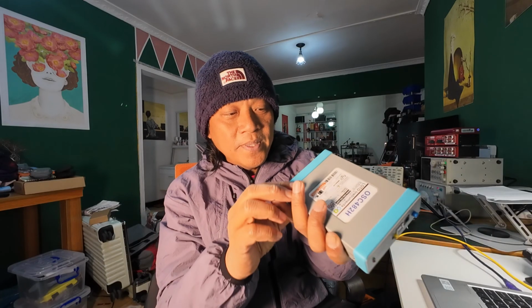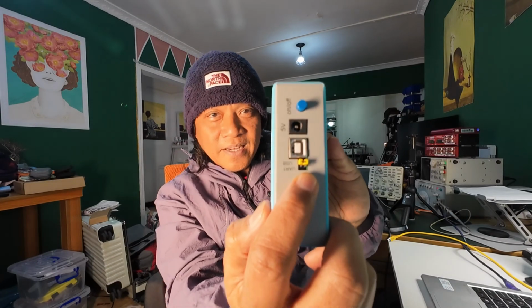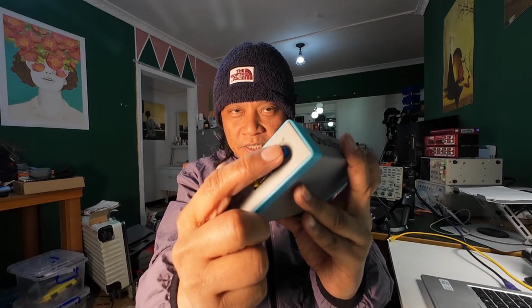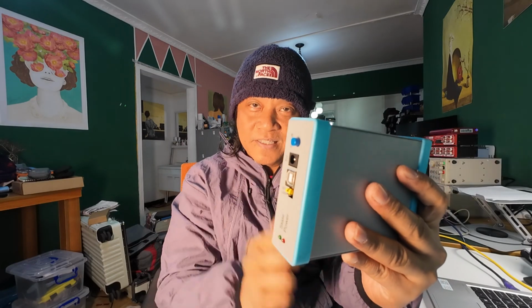So the model that I have here from Loto Instrument is the OSC482H. The preliminary hardware setting is to select between USB and UART, and I selected USB because I'm going to use the USB to power it on and also for the connection. You can see there is a switch here that you can push. If it is shorter, this is the power on mode, and when you press it again, it is longer, and this is the power off stage. That means it's on standby mode.